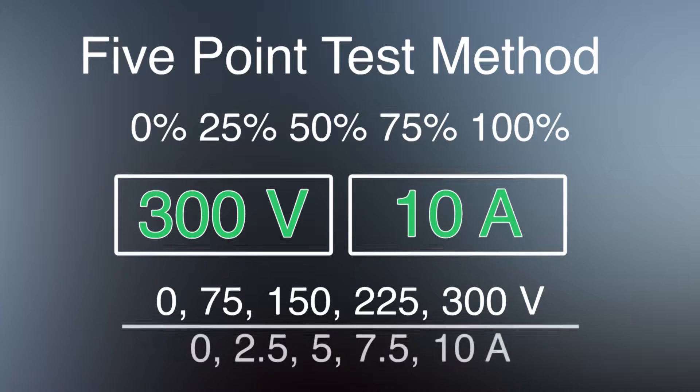The five point test method uses percentages of 0, 25, 50, 75, and 100%. For the 300 volt range we are testing here this corresponds to 0, 75, 150, 225, and 300 volts. Using the level ratio key allows for selecting of a percentage to conduct a point of the five point test. Similarly this test will be conducted on current as well. For this range of 10 amps, this leads to 0, 2.5, 5, 7.5, and 10 amps.